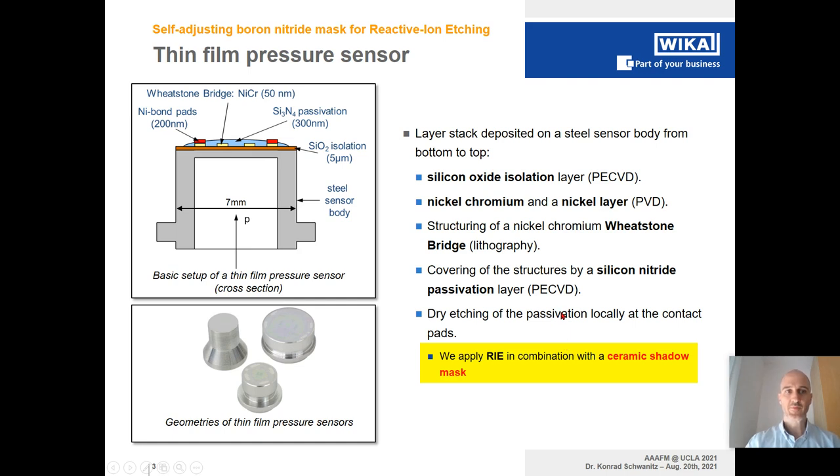Let me briefly introduce the principle of the thin film pressure sensor and its components. Starting with the stainless steel sensor body, displayed here in grey, with a typical diameter of seven millimeters. We can apply pressure inside to the membrane, which bends. Due to the bending, the nickel-chromium metalization changes its resistivity — aligned in a Wheatstone bridge — so we can extract an electrical signal. In between the polished sensor body surface and the metalization structure, we apply an electrical isolation deposited via plasma enhanced chemical vapor deposition: a silicon dioxide isolation layer with a thickness of about 5 microns.